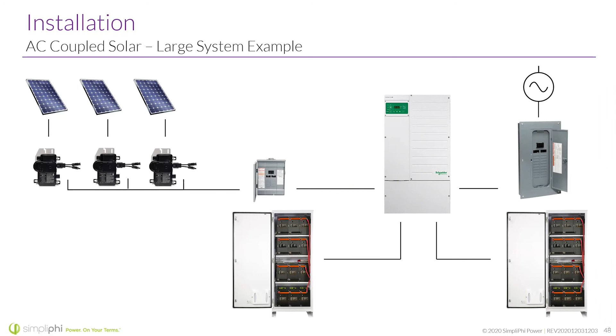If you're torquing the batteries and connecting the cables, please use a proper torque wrench: 160 inch-pounds, or 13.3 foot-pounds. Over-torquing the battery can cause damage. I always say this, but please check that your torque wrench is calibrated or recalibrated before you start using it on batteries.